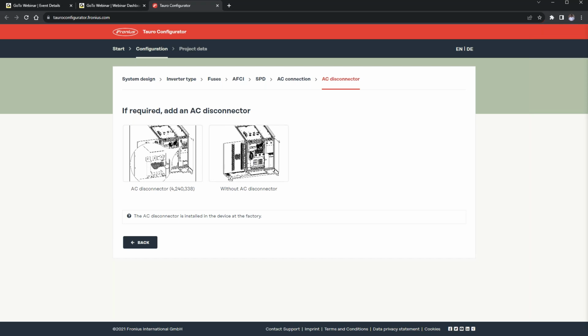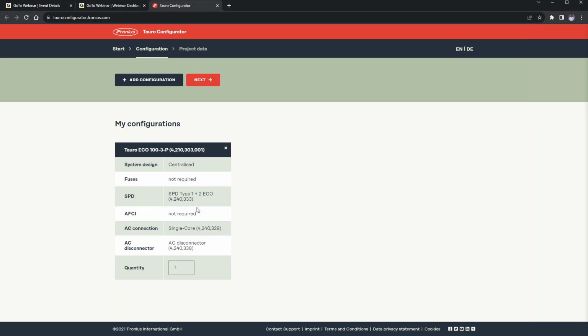Now you have the option of AC disconnector, which you can decide to include or exclude, as you can see. So if we include it, it's now going to take us to the page where we'll have a summary of the system configuration. So we have a centralized system where we don't have a fuse required, neither do we have an AFCI required in this case. An SPD protection type 1+2 implemented. AC connection is a single core version with AC disconnector, and then you can now select the quantity you want to make use of, either 1 or 6 or whatever value you want. So with this, you've been able to achieve a centralized system.